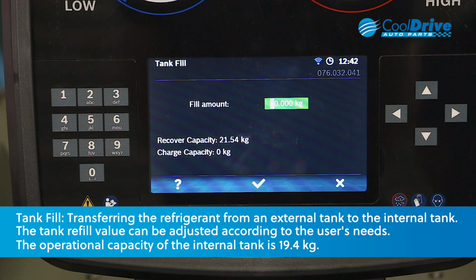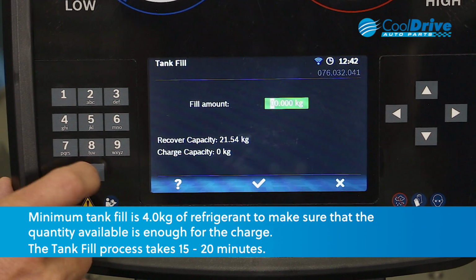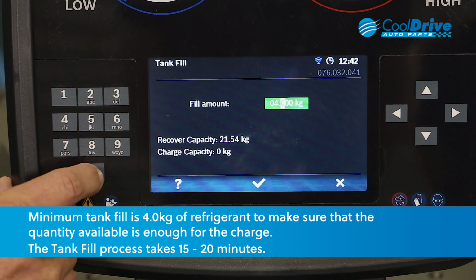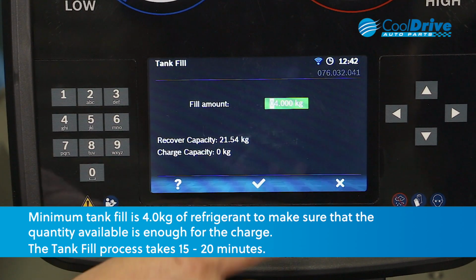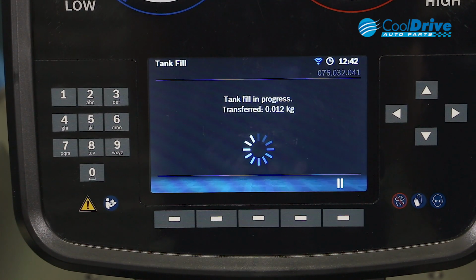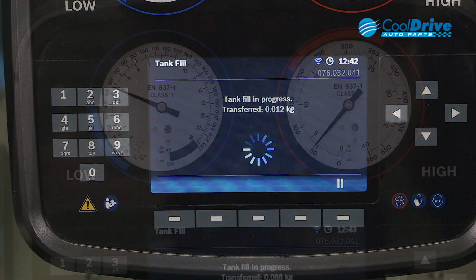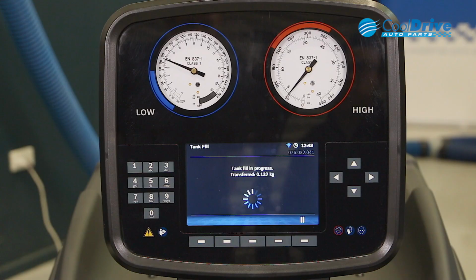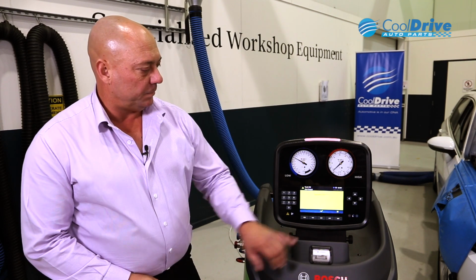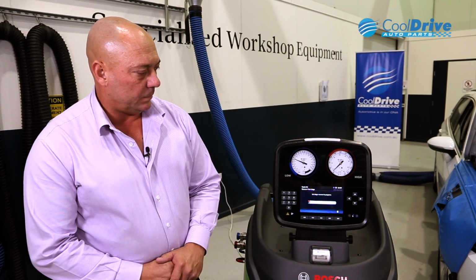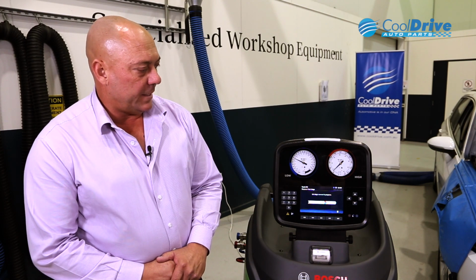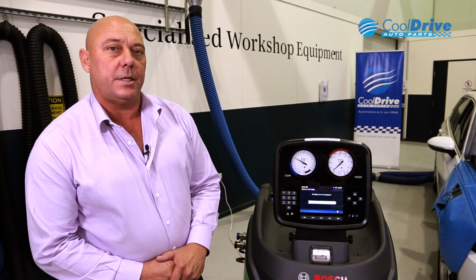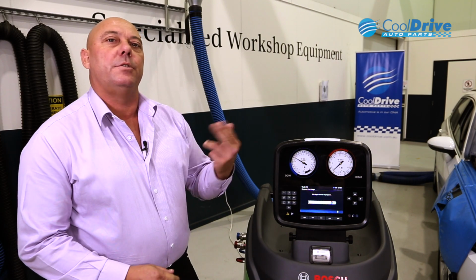Using the numerical keys on the side of the screen, we enter in how much refrigerant we need to fill. Our minimum requirement is 4 kilos, so we type in 4 kilos and then press enter. And our tank fill is now in progress. Once the tank fill is completed, it'll prompt you to disconnect the hoses. Then it enters into the first stage of a recovery process, where it's actually cycling the refrigerant through the machine.